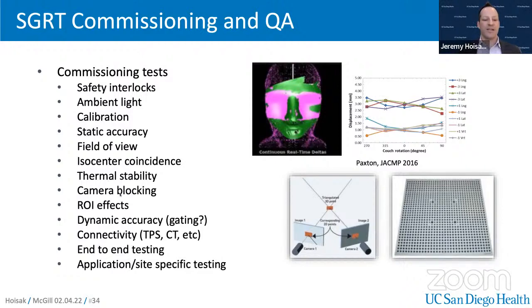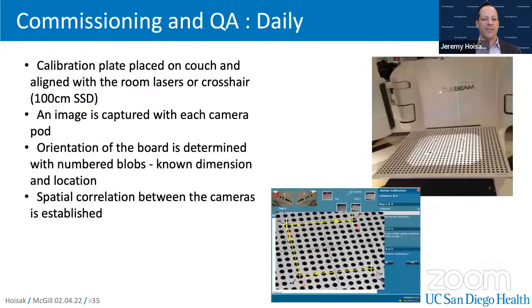Camera blocking, which I mentioned earlier, is important to quantify if you have a rotating gantry or other accessories in the room. Looking at the effects of ROIs and how dependent the system is on the size of the ROI is important. In addition to static accuracy, we need to evaluate dynamic accuracy, and evaluate connectivity with your treatment planning system or the CT, so we can import and export DICOM.